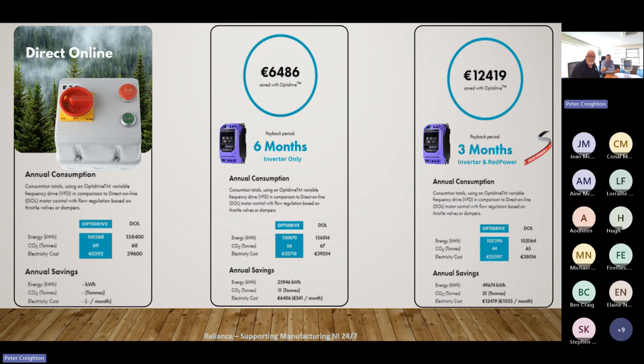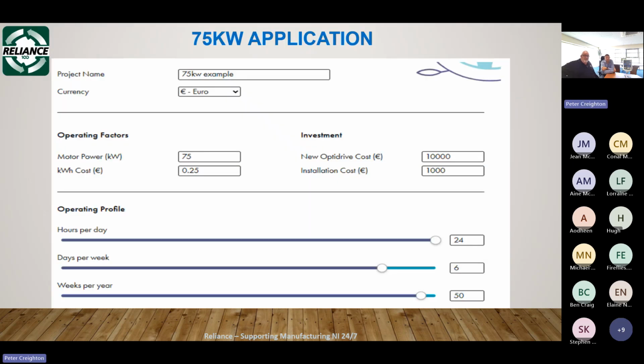I then looked at the second drive that they wanted me to look at, and it was a 75 kilowatt unit, yet again an old machine with no inverter, direct online, and these are the hours it was running. Similar, 75 kilowatts, 25 cents. The new Optidrive and belts and pulleys for this drive, because it was bigger, was 10,000 euros. It's still only the same installation cost because you're still only doing the same type of job. The hours match: 24, 6 days a week, 50 weeks a year.